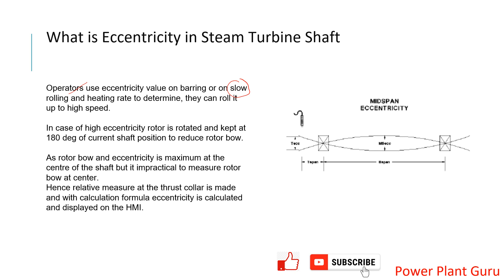What you can do is slowly rotate the shaft — maybe with a mechanical arrangement or using barring if it is possible — and rotate the shaft by 180 degrees. If the shaft is bowed downward due to gravity during the outage, you reverse it by 180 degrees so that the gravitational force now works to reduce the bow. You will then see the eccentricity value come down. When the values are sufficiently low, you can have barring started and slow heating started.